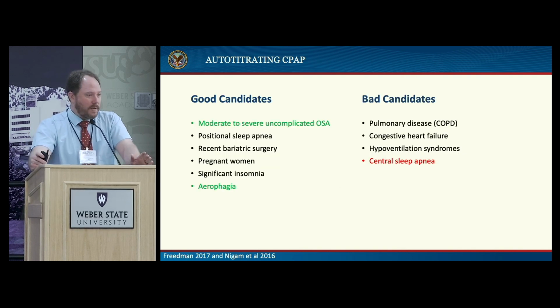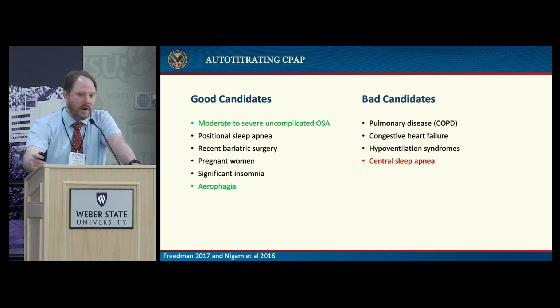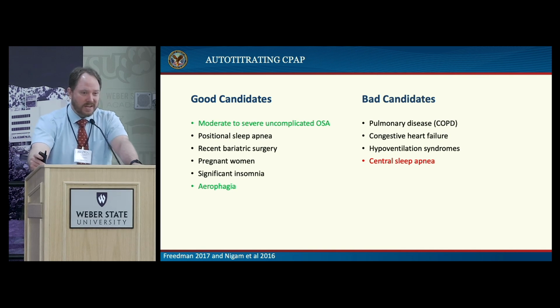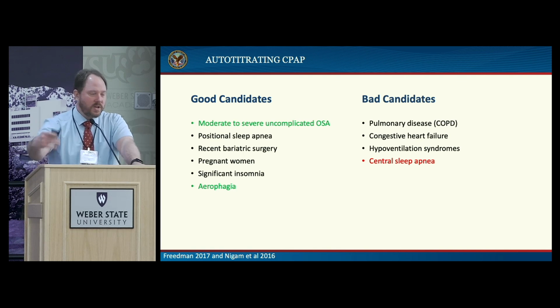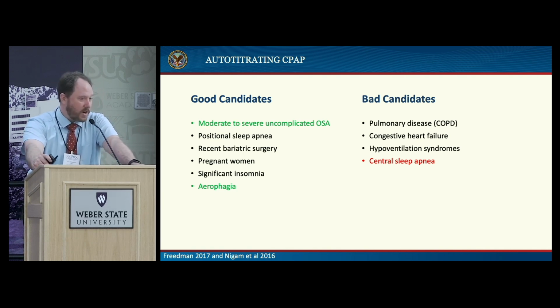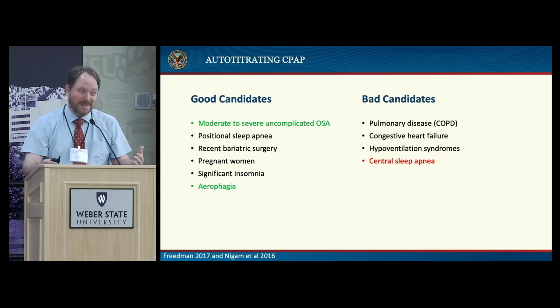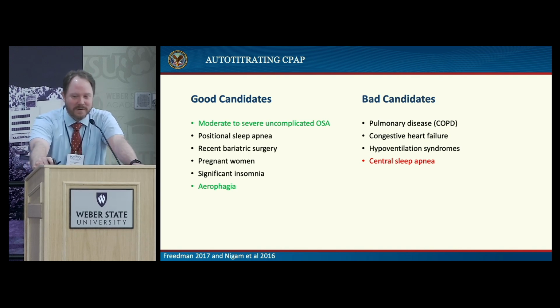Auto-titrating CPAP is going to be the mainstay of treatment still. Auto-titrating CPAP uses mathematical algorithms and analysis of the airflow and pressures through the air channel and makes determinations on whether or not the pressure is adequately maintaining the airway. So it looks at the shape of the inspiratory curve, it looks at the tidal volumes, it either increases or decreases airway pressure appropriately, or what it believes to be appropriately as programmed by the engineer.